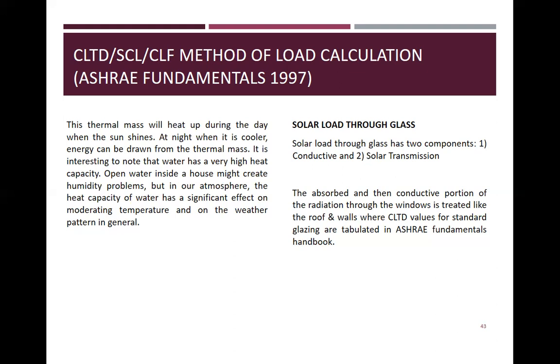Next, solar load through glass. Solar load through glass has two components, one conductive and two solar transmission. The absorbed and then conductive portion of the radiation through the windows is treated like the roof and walls where CLTD values for standard glazing are tabulated in ASHRAE Fundamentals Handbook.